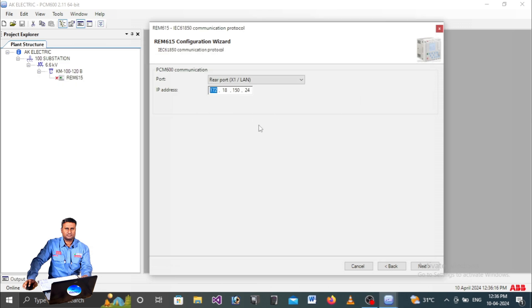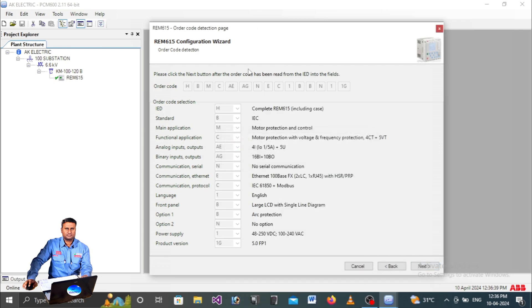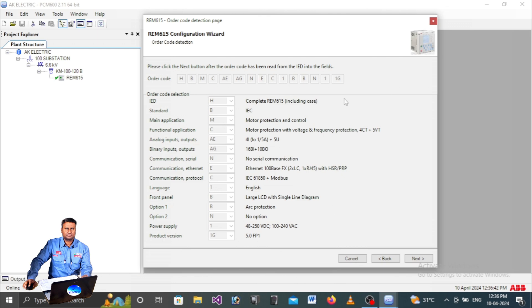Now let us check whether PCM600 is communicating with the relay. Enter the IP address - 24 - click Next, and the communication is established. The indicator turns green, confirming successful connection. The relay's order code is detected, and you can see the relay details including the product version, which is 5.0 FP1.